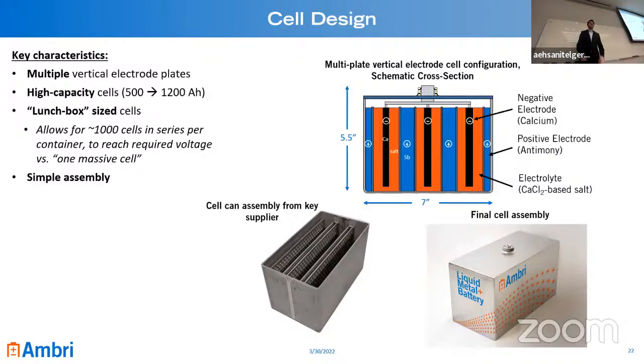Yes. Can you talk about round trip efficiency? Yes. Actually, the next slide I think mentions it, but because of our operating temperature and fast kinetics, we're getting 80 to 90% round trip energy efficiency, which is not quite as good as lithium ion, but better than lead acid, better than pumped hydro, some of the other competitors in the space, but we think very much good enough for this application.